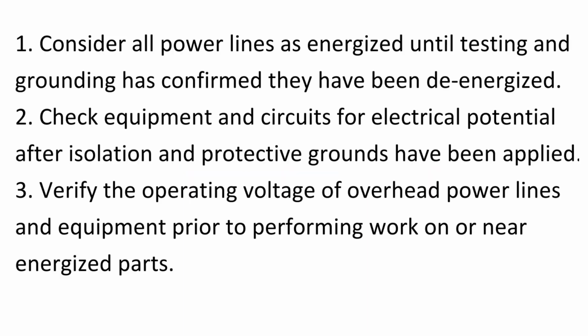Energized overhead power line. 1. Consider all power lines as energized until testing and grounding has confirmed they have been de-energized. 2. Check equipment and circuits for electrical potential after isolation and protective grounds have been applied. 3. Verify the operating voltage of overhead power lines and equipment prior to performing work on or near energized parts.